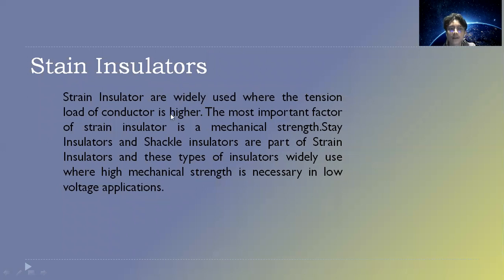Next, strain insulator. Strain insulators are widely used where the tension load of the conductor is higher. The most important factor of a strain insulator is the mechanical strength. Stay insulator and shackle insulator are part of strain insulator, and this type of insulator is widely used where high mechanical strength is necessary in low voltage applications.